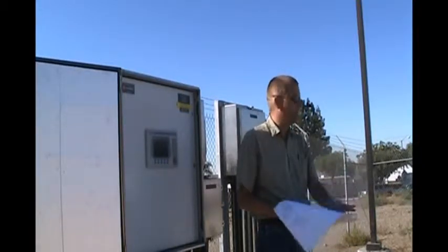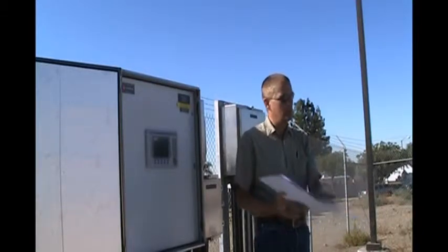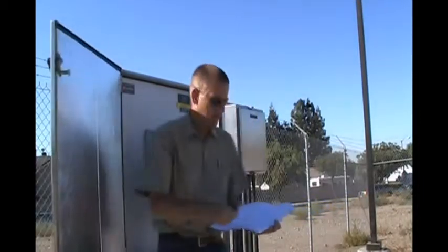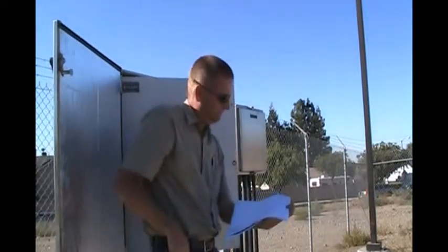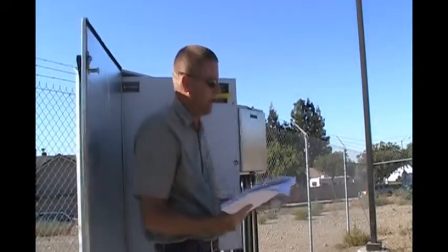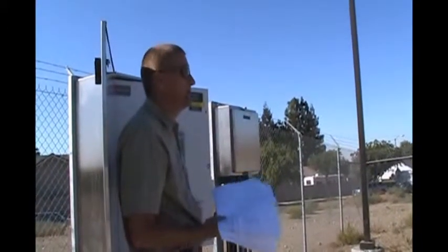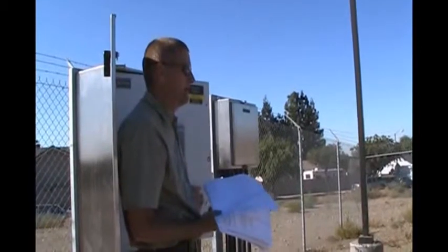We start with 120 volts. This is the 120 supply in this panel. On the left-hand side, you'll have everything that's connected directly to utility power, and then everything on the right is everything that's hooked to the UPS power, with the UPS being on the top right. So on the left-hand side, we have the operator interface here, and the heater and the AC are the only things connected to the utility power directly.